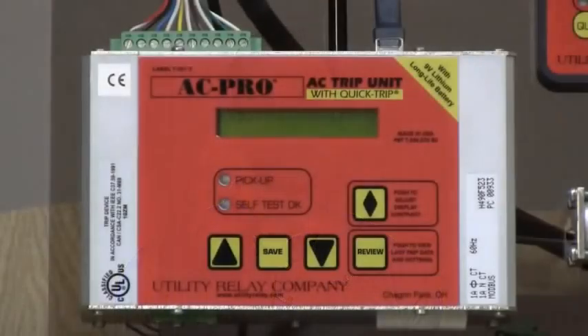Utility Relay Company is an industry leader in the manufacture of true RMS solid-state trip units for 600-volt class circuit breakers. Utility Relay Company is focused on doing one thing, providing retrofit kits for circuit breakers. We have over 1,000 kit designs available and are adding more as the need arises. Utility Relay Company strives to provide exceptional products and exceptional service. In this video, I will go over the basics of the AC Pro trip unit.